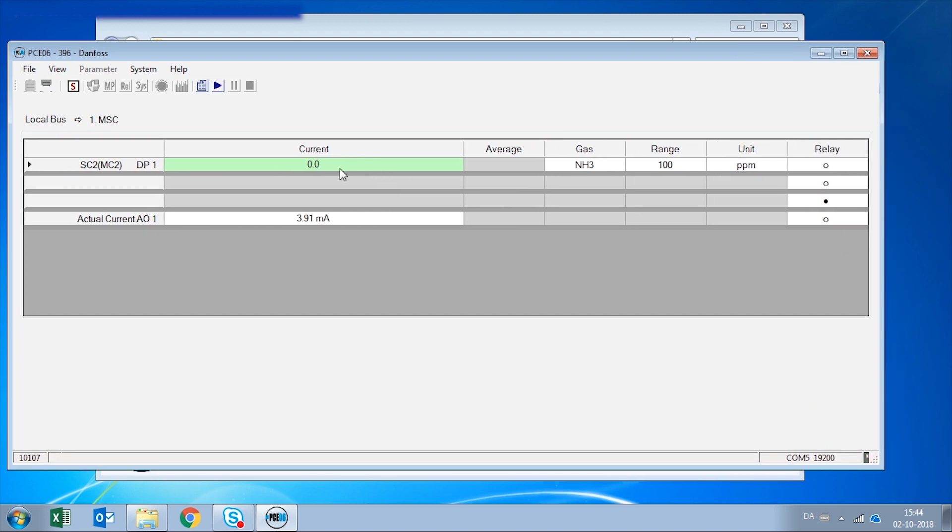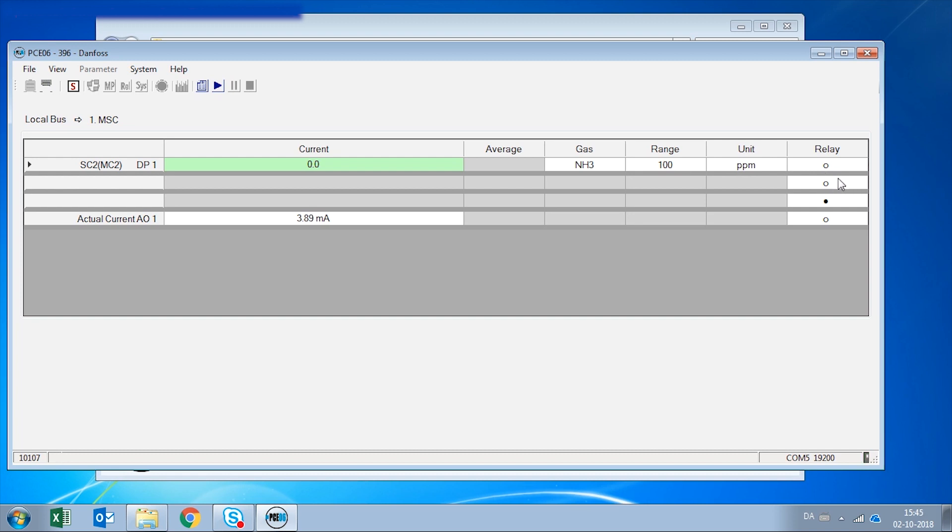The current value is 0 ppm. It is an ammonia sensor on the range from 0 to 100 ppm and here you can see the status of the relays. Relays 1 and 2 are not energized because there is no alarm and safety relay 3 is energized as it should be. You can also see the 4 to 20 milliamp output.